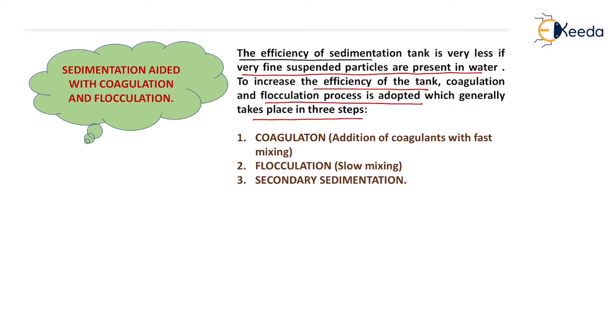The whole process of sedimentation aided with coagulation and flocculation generally takes place in three steps. The first step is coagulation, in which we add the coagulant and do fast mixing so as to spread the coagulant uniformly in the water. After the coagulation process we go for flocculation, in which we mix the water slowly so that floc formation occurs. When the flocs are created, we send the water into the secondary sedimentation tank, where sufficient detention time is provided and all the flocs settle down. The water will then be pure and ready for the next treatment, that is filtration.